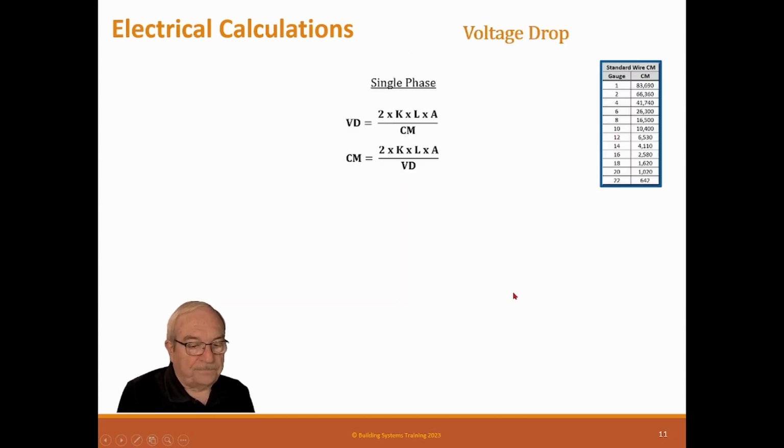Okay, voltage drop. Voltage drop is important if you're in construction. The engineer is supposed to lay all this out, but a lot of times there are things engineers don't lay out, like control voltages. So if you have a transformer for a controller and you're going to run a wire out to it, and you run it for very long, or vice versa, you have an electrical circuit designed for a transformer for a controller, and it goes right there, but the controller is 100 feet away.